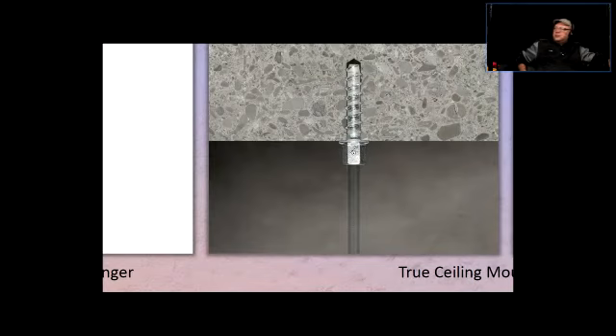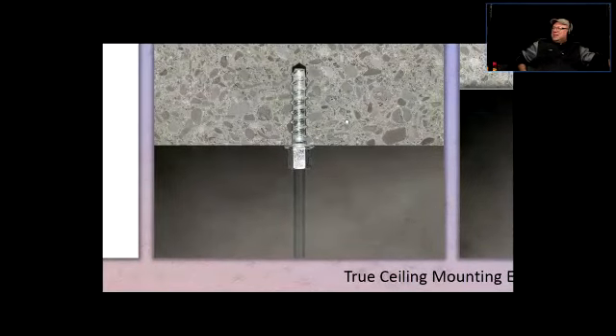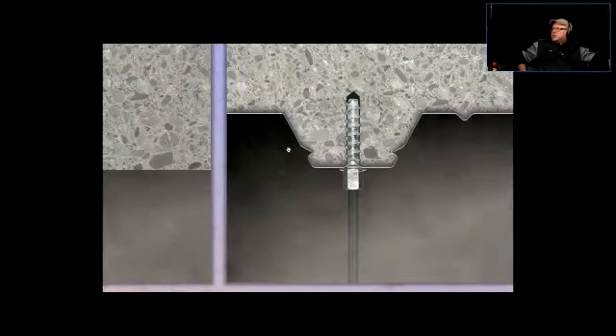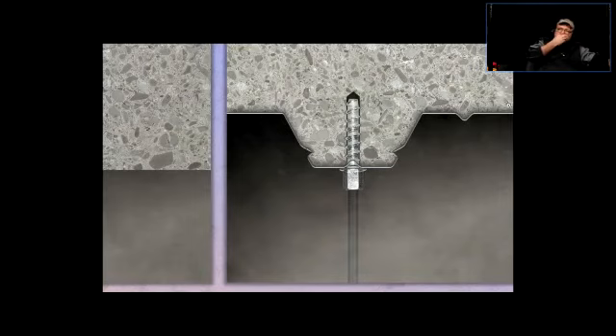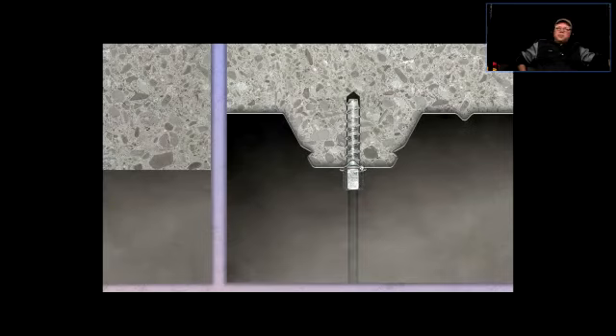Do not use a hammer drill to drive the anchor in — just use a regular drill. You don't want any impact because you'll shatter the opening and won't have as much hold. For a concrete ceiling, sometimes you have bare concrete and sometimes there's perforated steel covering it. To drill through that, first use a steel drill bit without hammer action to punch through the steel, then change to a concrete bit and use hammer drill action for the concrete portion.